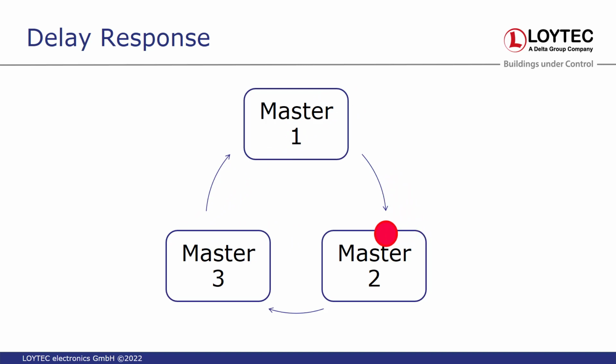And if one device does not respond, then the token gets lost. So the device tries to give the token to the next device, sees that the token is not passed on, and tries again. After, I don't know, 3 retries, somebody needs to regenerate the token because the token is just lost on the network, it's dropped. And this, of course, slows down the whole communication.